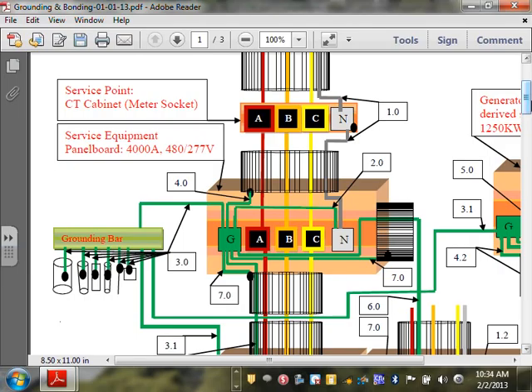I don't know of any engineering firm or any contractor who does only one. But the code says, guys, you only need 1. But if others exist, you must bond to them. So it's like a catch-22. If you have a water pipe and you have a concrete encased electrode, the foundations of a building tied to the foundation, based on the code, you're done because you have 1, but you have to bond to the water pipe. Well, guess what? Now the water pipe becomes part of your grounding electrode system. So you only need 1, but if others exist, you must bond to them.